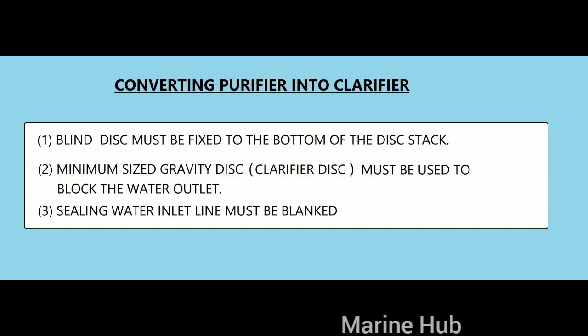Converting purifier into clarifier: A blind disc must be fixed to the bottom of the disc stack. Minimum sized gravity disc, the clarifier disc, must be used to block the water outlet. Sealing water inlet line must be blanked.